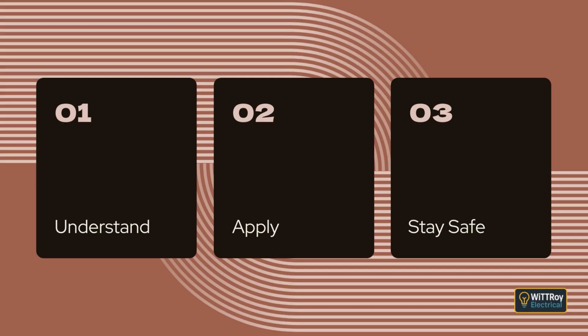To meet those safety requirements, installation work must follow good, safe practice. The standard highlights several key considerations. First, the equipment must be suitable for the environment. It must cope with the temperature, weather, mechanical forces, or any other environmental conditions where it is installed. Any built-in protection must still work after installation, and extra protection, such as an enclosure, must be added if needed. Second, the manufacturer's instructions must always be followed. Third, enough space must be provided for safe operation, inspection, testing, and maintenance. Fourth, mechanical fixings must be strong enough. Brackets, screws, and supports must hold the equipment securely and remain durable over time.